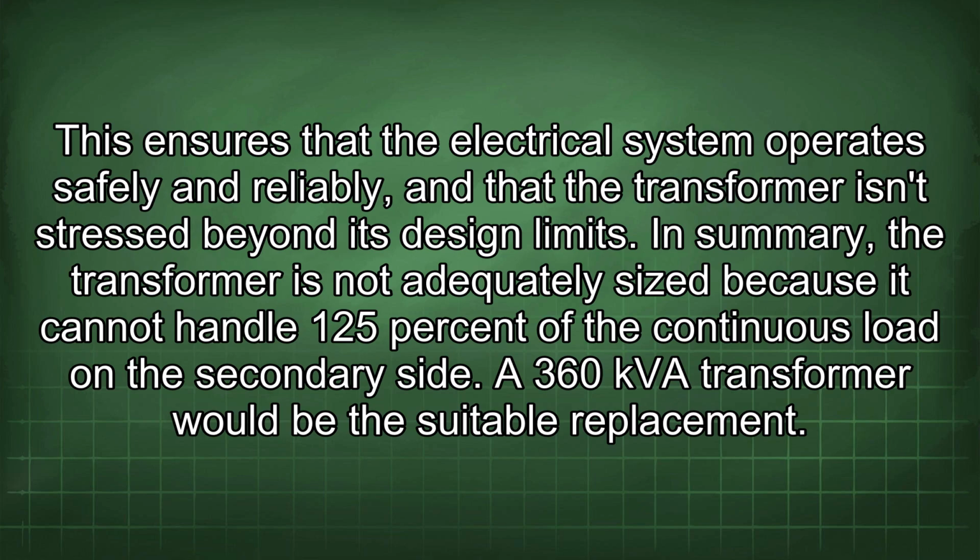In summary, the transformer is not adequately sized because it cannot handle 125% of the continuous load on the secondary side. A 360 kVA transformer would be the suitable replacement.